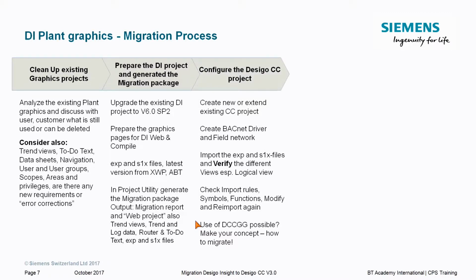So, Pino, does that mean you have to have the web created as well, as a requirement for the migration? You have to, the Desigo Insight Web component? You have to do the same process. So the question was, is it needed to do the web project? Yes, it is the same workflow as you would prepare for a Desigo Insight Web project. Yeah, because you create the XML files there, basically. And exactly those XML files are needed for the mapping, to convert.